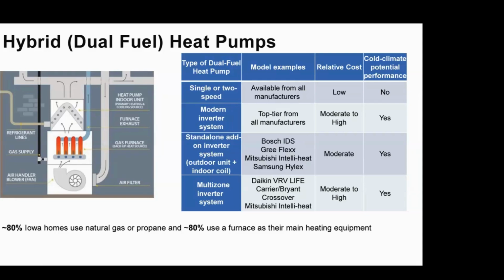So what that allows you to do is take advantage of the situations where it's most economically advantageous to use the heat pump. Basically, when it's above a certain outdoor temperature threshold, you rely on the heat pump, and below that threshold, you use the gas furnace. That threshold can be user defined - you'll have an outdoor sensor included with your thermostat that you program, so the thermostat knows that, for example, at 20 degrees and above, the heat pump runs, and below 20 degrees, the gas furnace kicks in. This is kind of the sweet spot for the upper Midwest, where gas rates tend to be low and electric rates tend to be high. Thinking about it in terms of dual fuel probably makes the most sense for most folks.